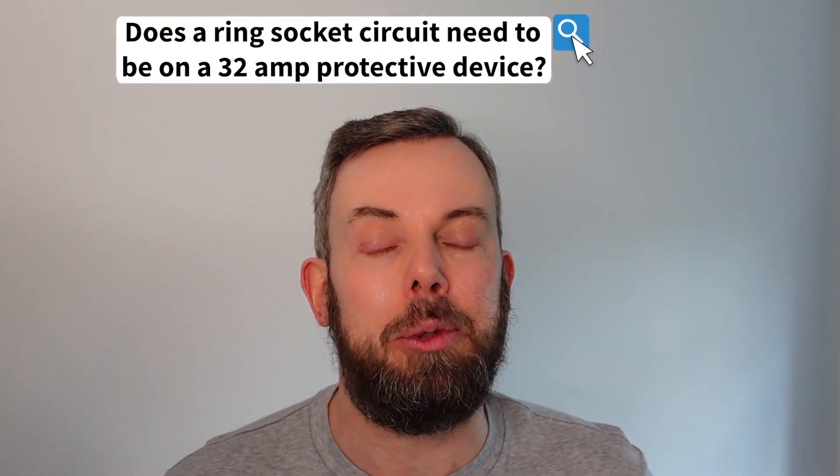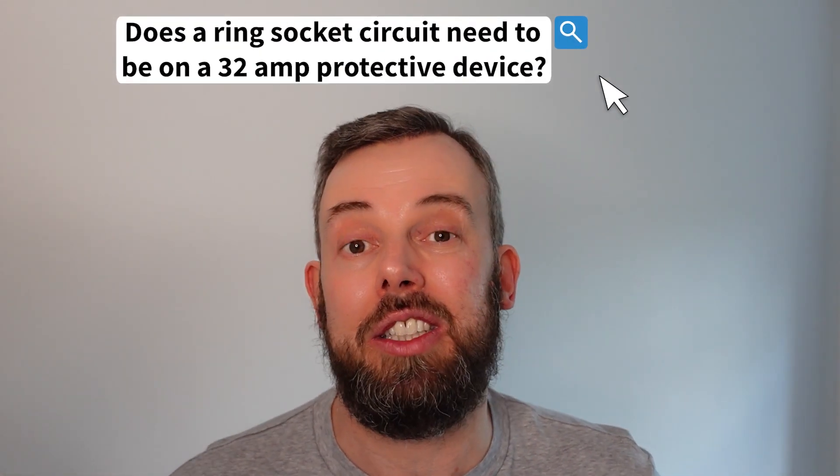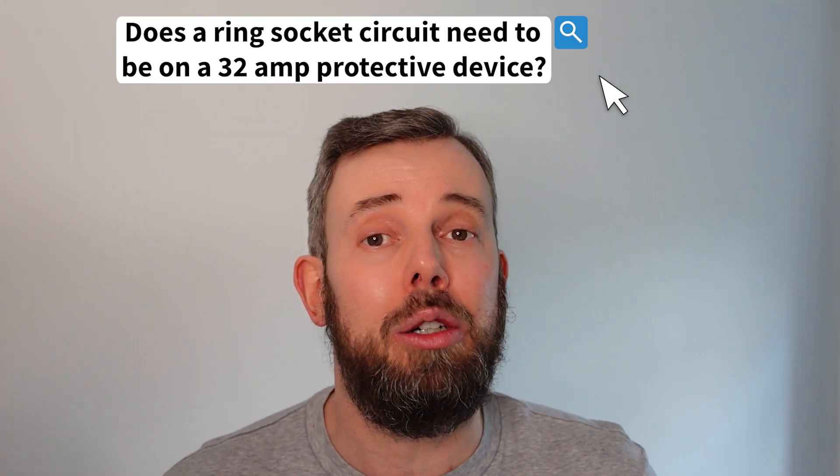Does a ring socket circuit have to be protected by a 32 amp protective device, or could you use a lower rated protective device than that? If we look in the wiring regulations, regulation 433.1.1 requires that the rated current of the protective device is not less than the design current.